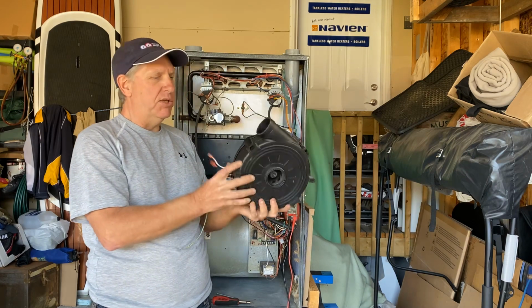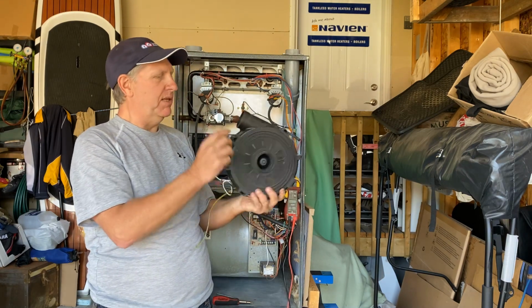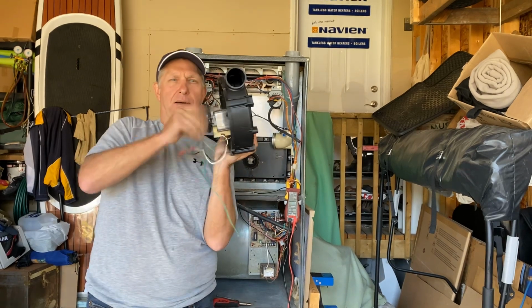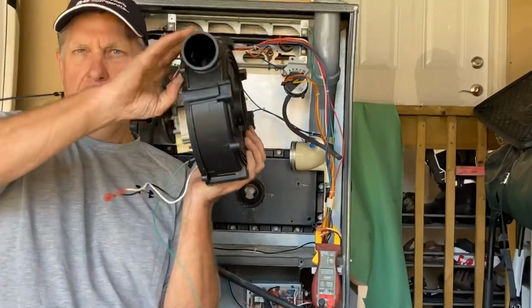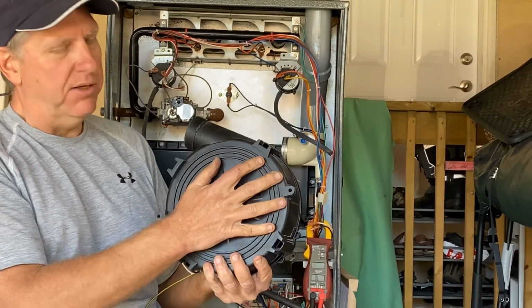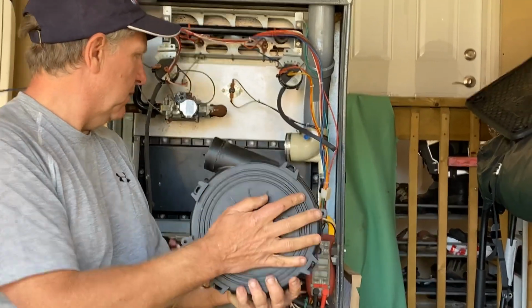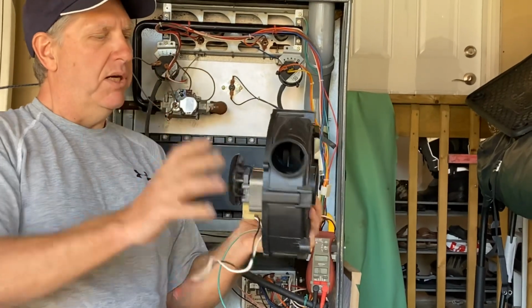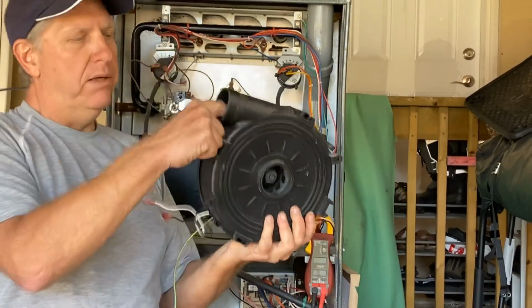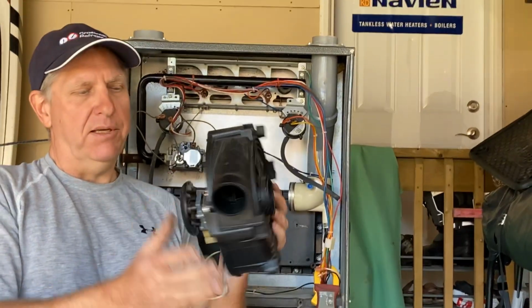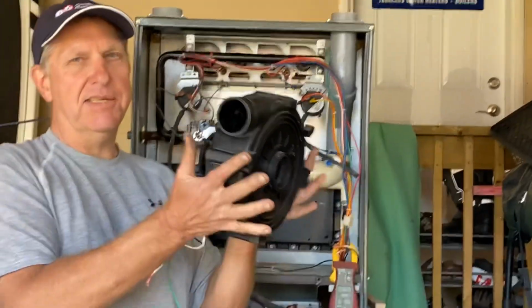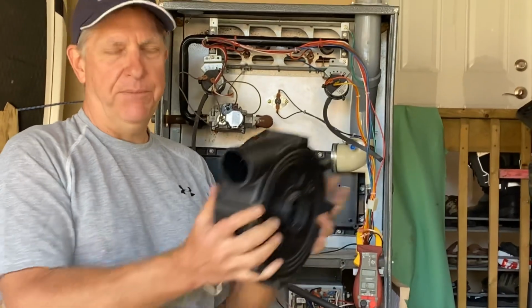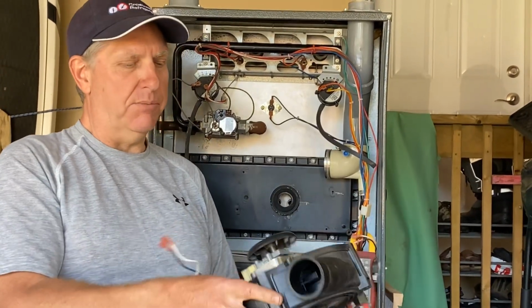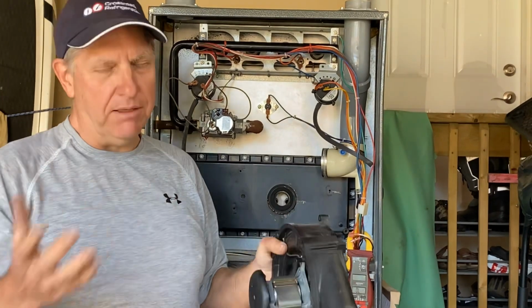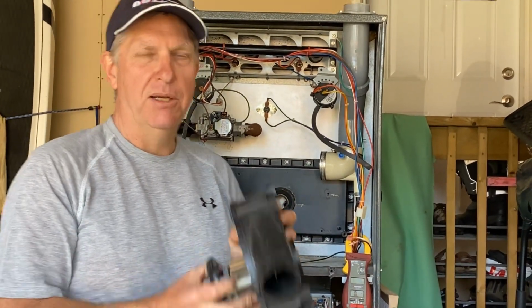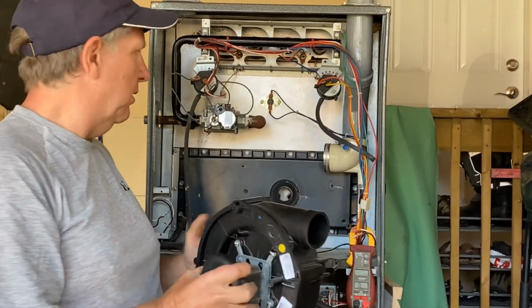The venter motor assembly is out. You can't really see in there too well, but it's like a little blower. This turns, the motor turns, blows the air through, sucks the air in here through the heat exchanger, sucks it through here, blows it out here. So motor, wheel, a number of things can go wrong with this. Generally you're going to buy this as an assembly, just take one out and put the other one in. You're not going to take this apart and repair or replace motors. You can if you're really in a bad pickle, but generally you're just going to replace the whole assembly.